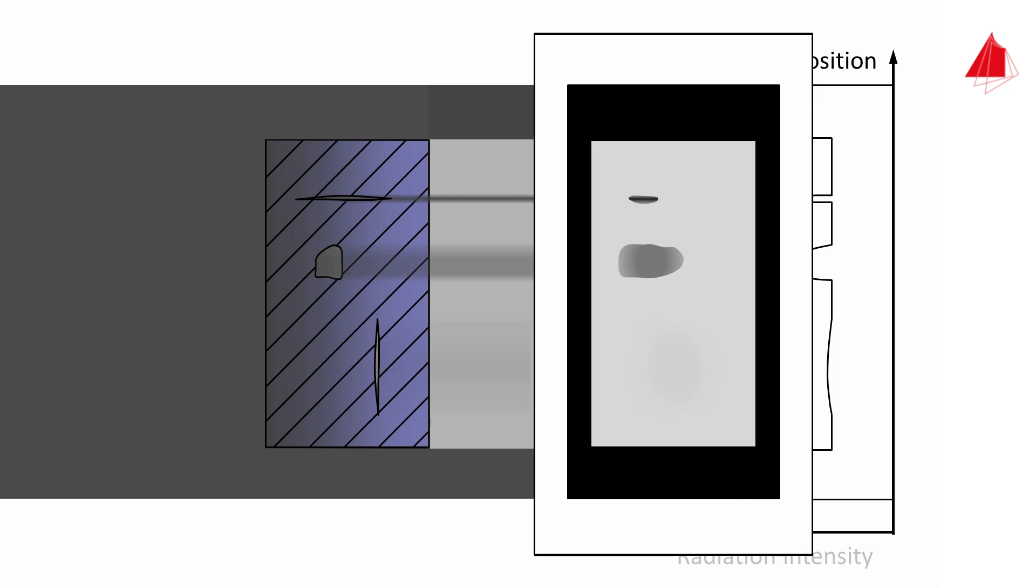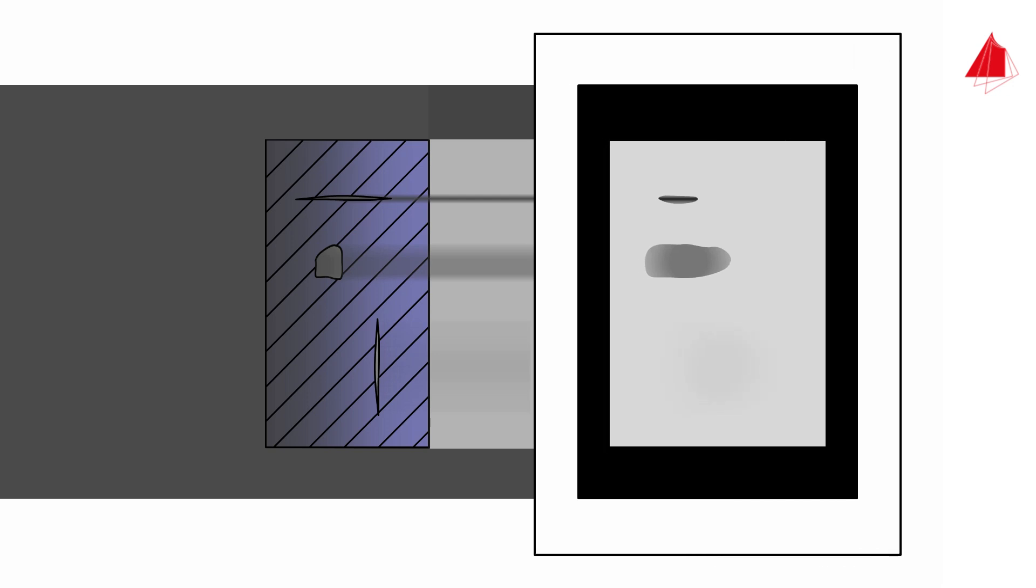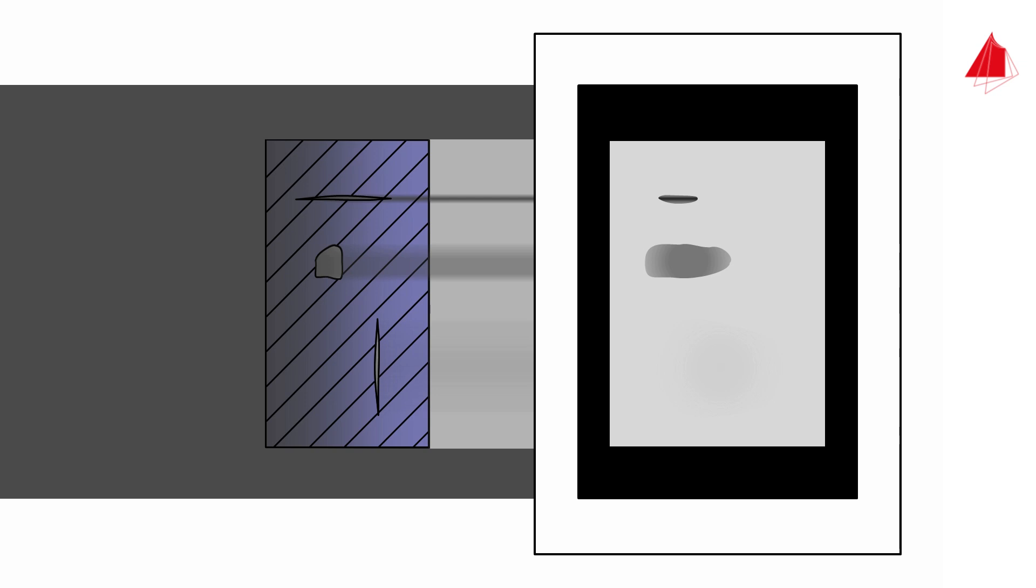And this is what the complete x-ray image of the sample looks like. The originally depicted sectional plane of the sample is shown as a dashed line. Places with defects appear darker because more intense radiation reaches the image capture unit. As expected, the vertical crack is virtually undetectable.